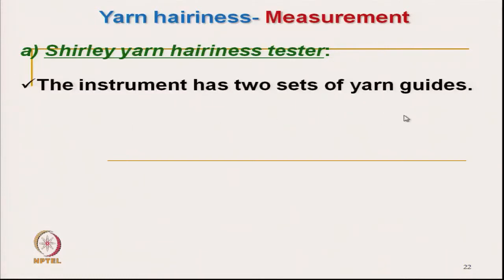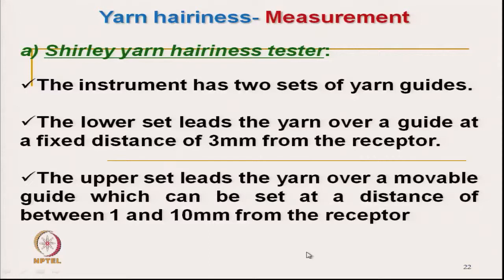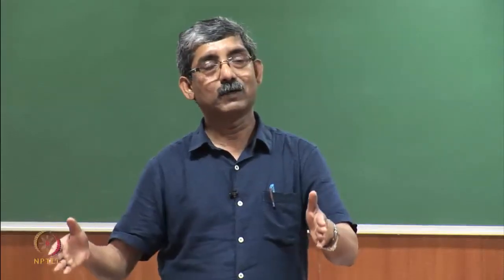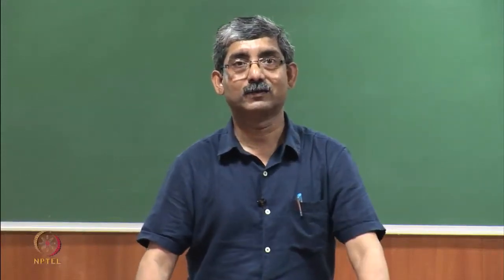The instrument has 2 sets of yarn guides: the lower guide gives a fixed length of 3 mm and the upper guide gives a variable set of lengths. The total number of hairs in a fixed length can be counted, and if we know the speed of the yarn, we can convert it to the number of hairs per unit length.